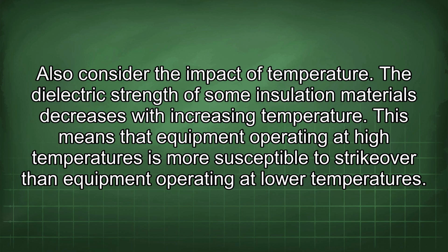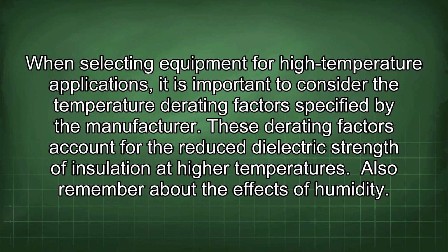Also consider the impact of temperature. The dielectric strength of some insulation materials decreases with increasing temperature. This means that equipment operating at high temperatures is more susceptible to strikeover than equipment operating at lower temperatures. When selecting equipment for high-temperature applications, it is important to consider the temperature derating factors specified by the manufacturer. These derating factors account for the reduced dielectric strength of insulation at higher temperatures.